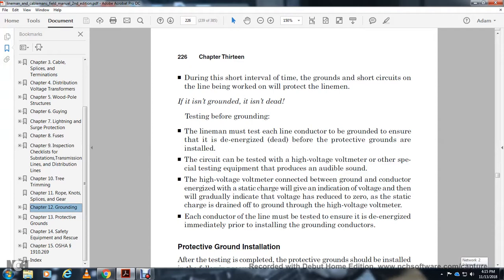Testing before grounding. The lineman must test each line conductor to be grounded to ensure that it is not energized before the protective grounds are installed. The circuit can be tested with a high voltage voltmeter or with special testing equipment that produces an audible sound. A high voltage voltmeter connected between the ground and a conductor energized with a static charge will give an indication of voltage, then will gradually indicate the voltage has reduced to zero.